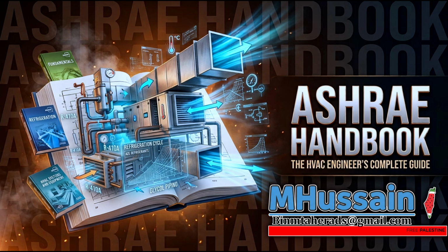You are no longer just designing a room to hold a chiller. You are designing a room that requires active leak detection sensors, automated purge ventilation systems to instantly exhaust the gas, and in some extreme industrial cases, blast-resistant construction. A chemical tweak in Volume 3 literally adds reinforced concrete and specialized exhaust shafts to the architectural blueprint in Volume 4. It's all deeply connected.